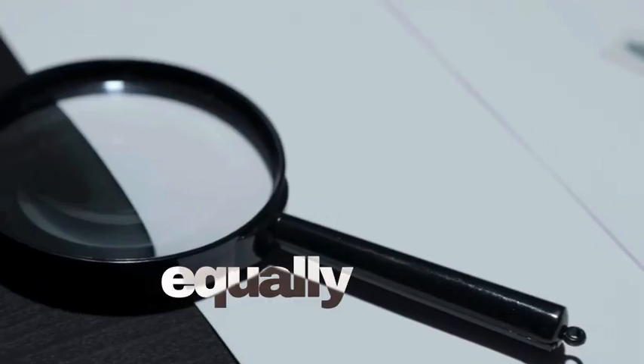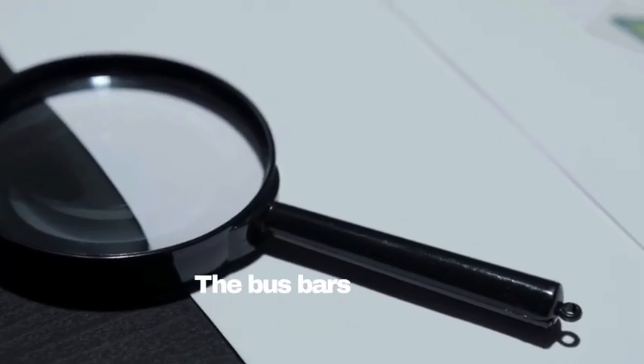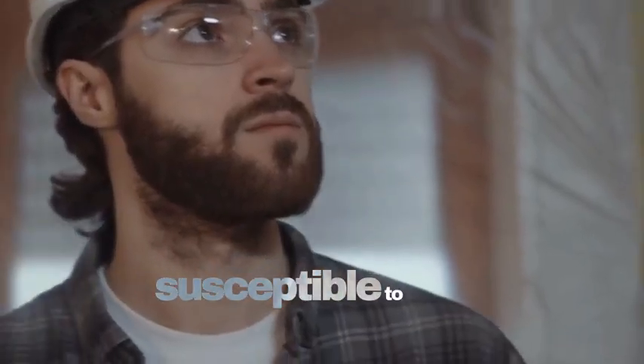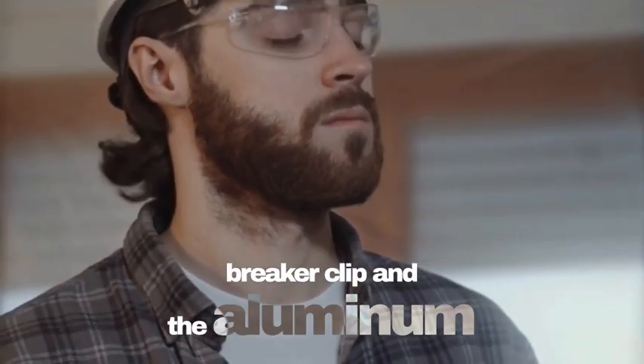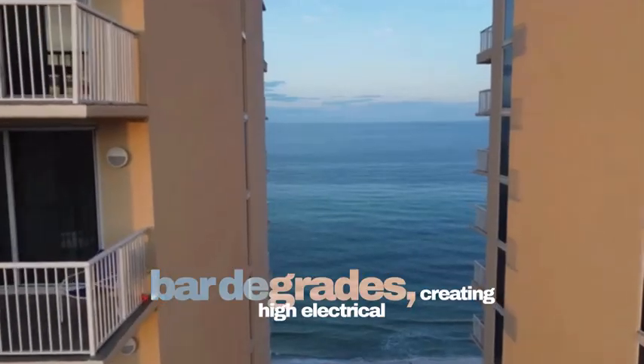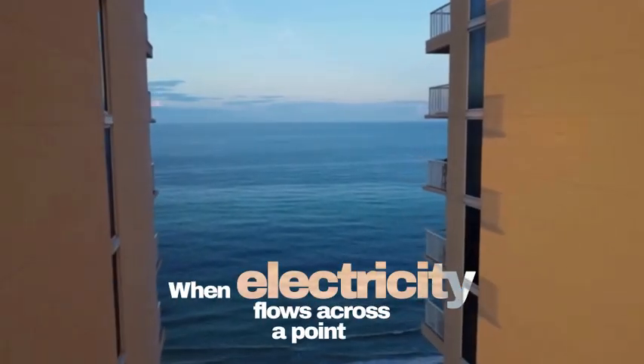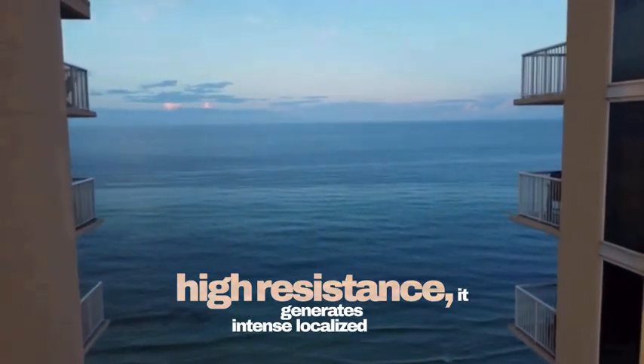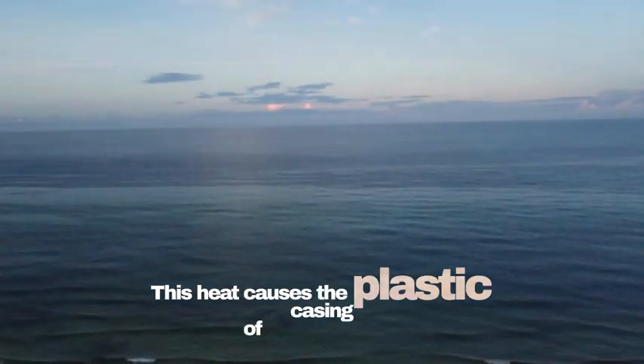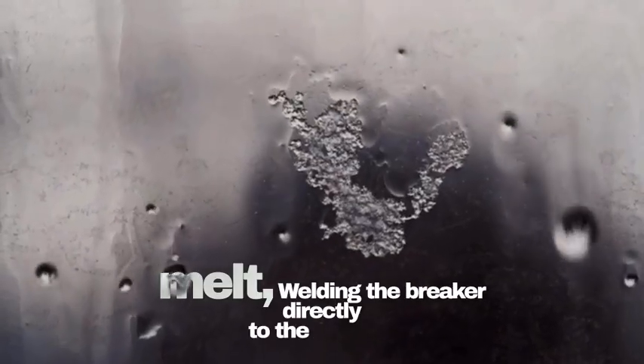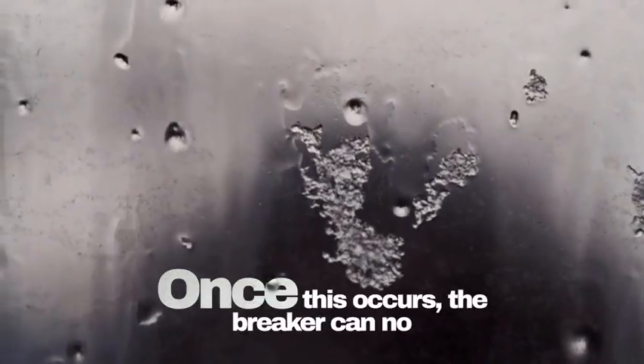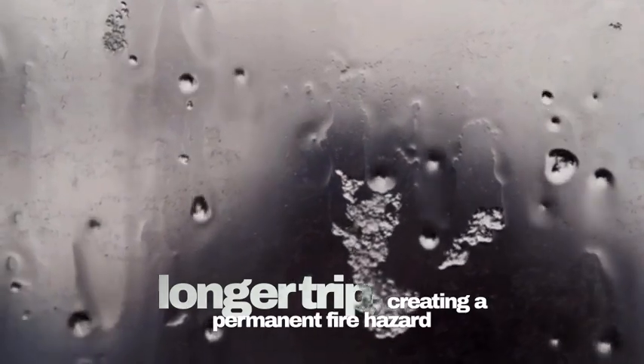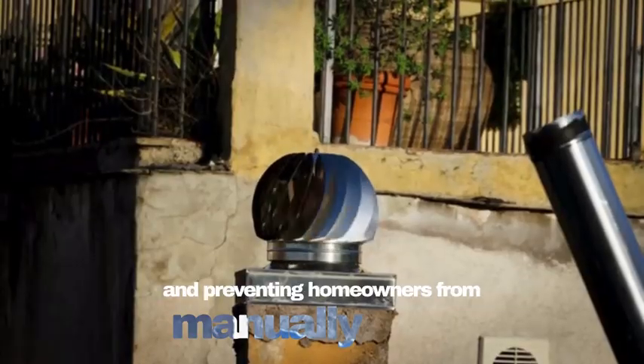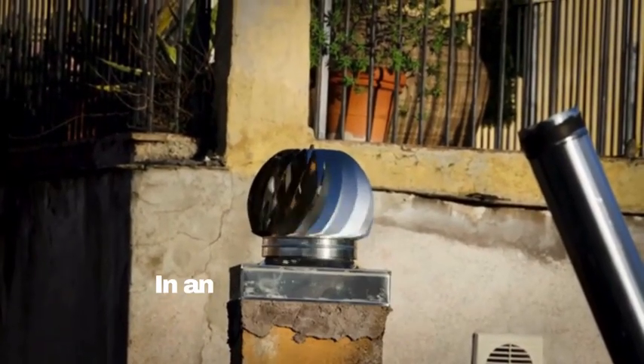Zinsco panels feature an equally dangerous failure mechanism. The bus bars inside a Zinsco panel were manufactured using an aluminum alloy that is highly susceptible to oxidation and mechanical deformation. Over time, the connection between the breaker clip and the aluminum bus bar degrades, creating high electrical resistance. When electricity flows across a point of high resistance, it generates intense localized heat. This heat causes the plastic casing of the breaker to melt, welding the breaker directly to the bus bar. Once this occurs, the breaker can no longer trip, creating a permanent fire hazard and preventing homeowners from manually shutting off power to that specific circuit in an emergency.